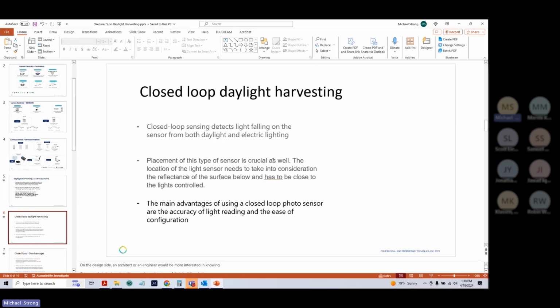Also, main advantages of using a closed loop photo sensor are the accuracy of light reading and the ease of configuration, right? Because we're just measuring both, and we don't have to separate the two. And you'll see where the difference lies here in just a second. But let's look at some of the disadvantages. So the main advantages are ease and accuracy, because we're going to read both artificial and natural lighting, and then we're going to configure average foot candle readings and make the lights react to an average of 20-foot candle, whether it's sunny or it's nighttime.